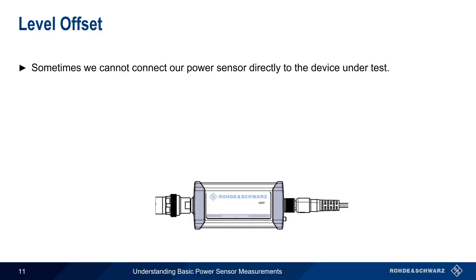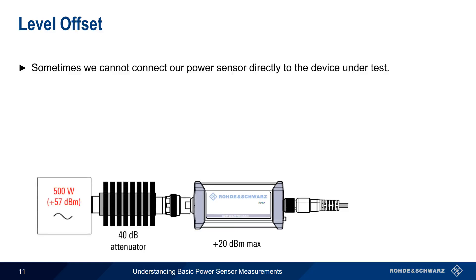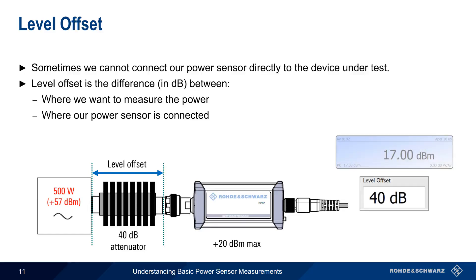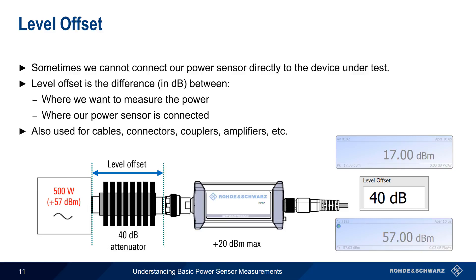In some cases, we can't connect our power sensor directly to the device under test. For example, all power sensors have a maximum input power which should never be exceeded in order to avoid permanent damage to the sensor. When we need to measure power levels above this limit, we use an attenuator to bring the power level down to an acceptable level. If, however, we want our measurement results to be expressed in terms of the pre-attenuator power, we can add a level offset. A level offset is basically the difference, in dB, between where we want to measure power and where the power sensor is attached. For example, if we use a 40 dB attenuator to measure a 500 watt or 57 dBm source, we get 17 dBm; adding a level offset of 40 dB would make our measurement result read 57 dBm. Level offset can also be used to compensate for losses in cables, connectors, and directional couplers between the device under test and the power sensor.